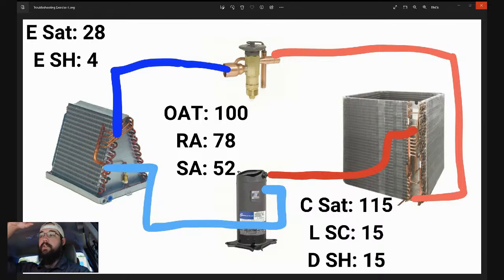So coming in, we can't pull the coil today. We've got to clean this thing regardless. Hot water. One of my favorite tricks is getting a cup, not even my pump up sprayer, but a cup of hot water, as hot as whatever they have on site, and heavily soaking that coil in just hot water, and letting some of that growth and whatever is on there try to seep out of that coil.